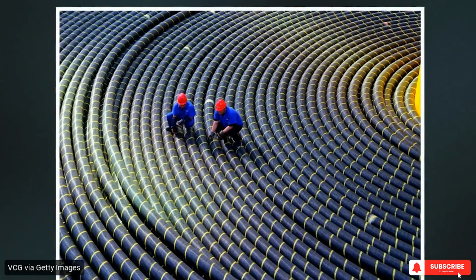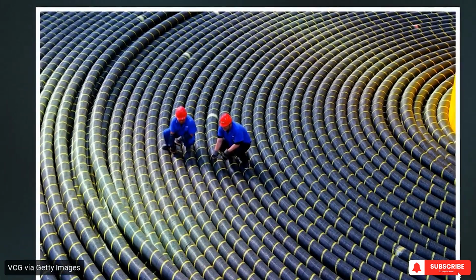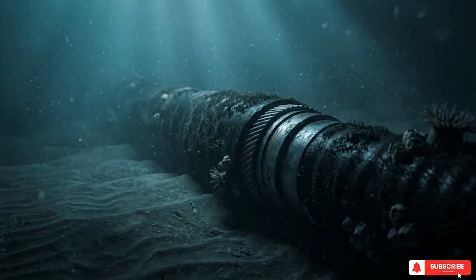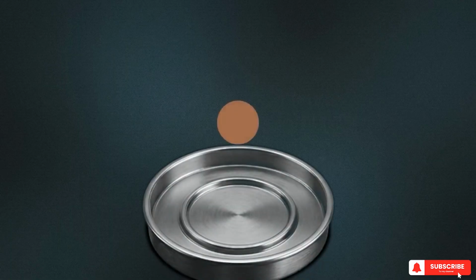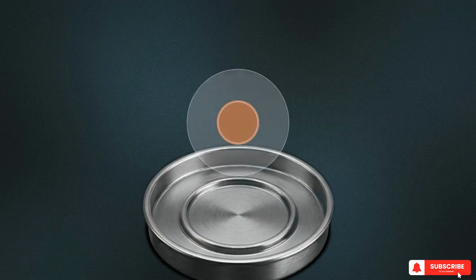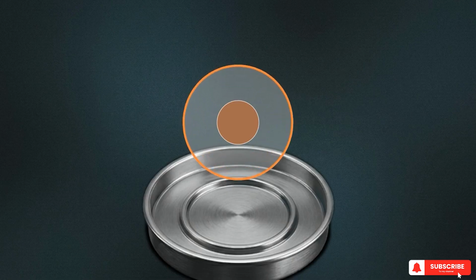The workers standing on these coiled lines highlight their massive physical scale. These are heavy, multi-layered structures engineered to endure decades of extreme environmental stress on the seafloor. Inside, a central copper or aluminum conductor carries the current, surrounded by a thick layer of cross-linked polyethylene, or XLPE. This specialized plastic insulation prevents the incredibly high voltage from breaking out of the cable and discharging into the sea.